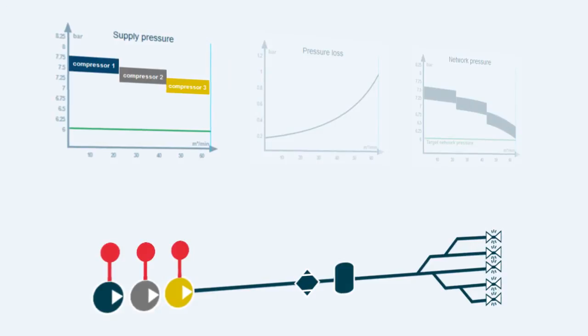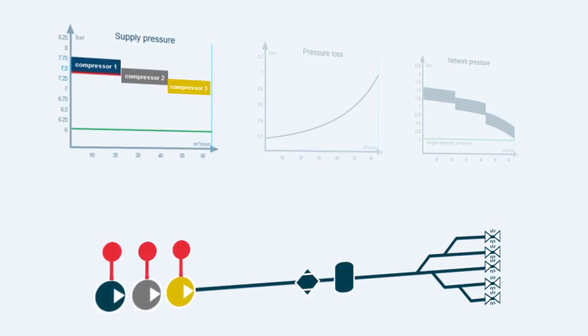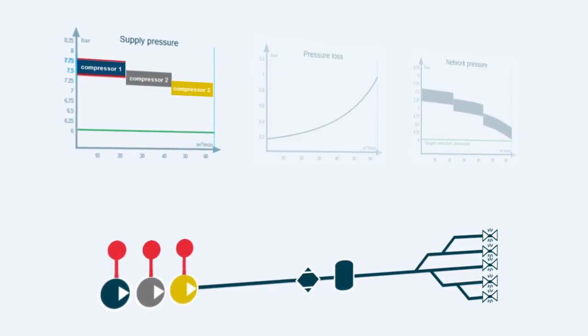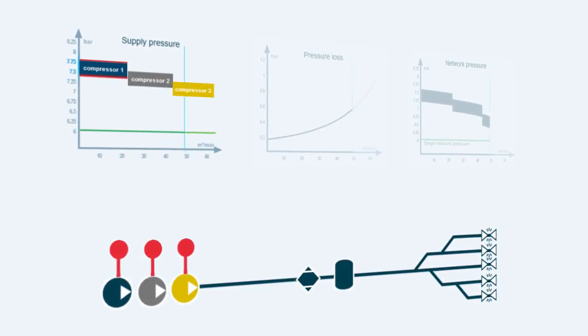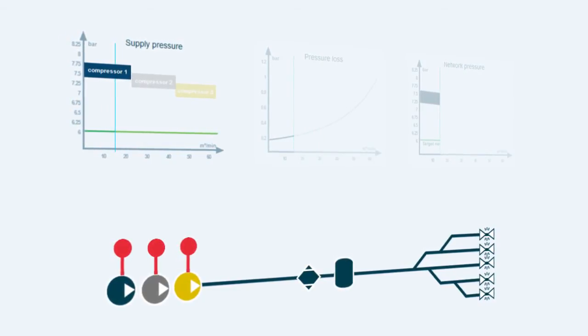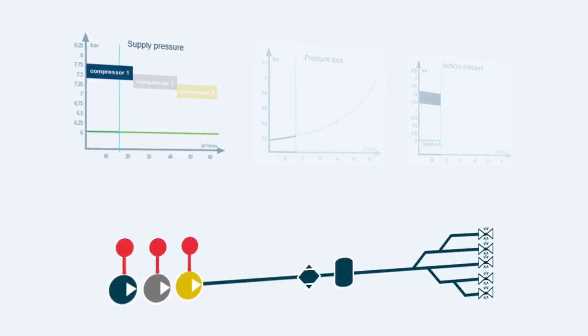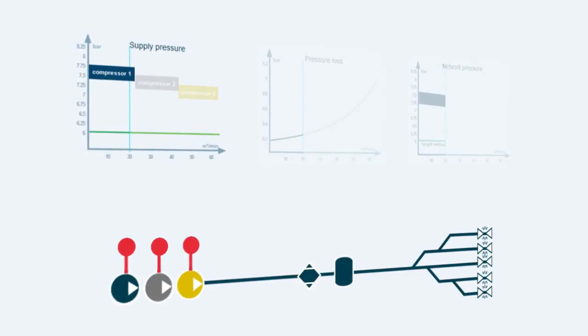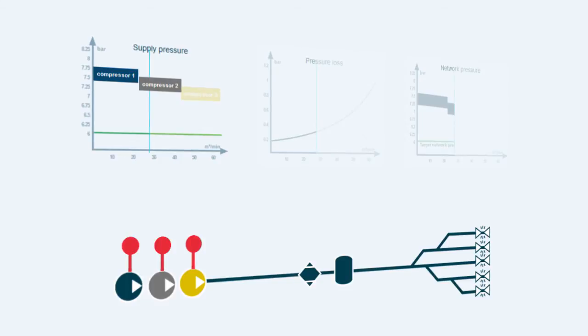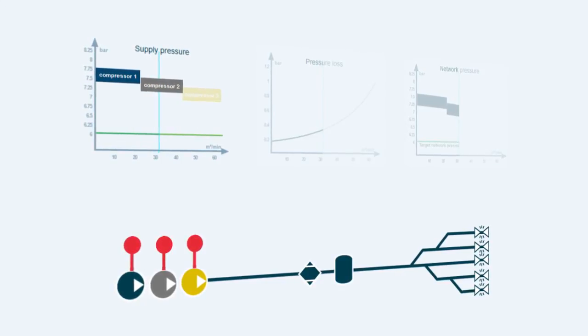Compressor 1, for instance, starts compressing air at 7.5 bar and stops at 7.75 bar. When air consumption is less than the capacity of compressor 1, it can compress the necessary air alone. As air consumption increases, and its capacity is no longer enough to maintain the pressure, the next compressor starts according to its pressure setting.